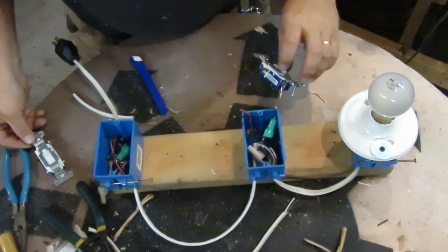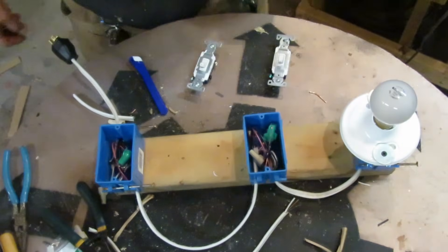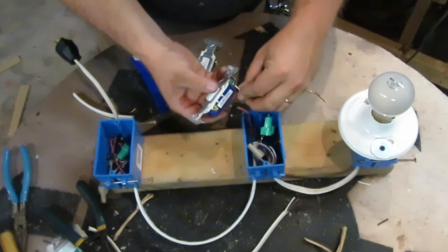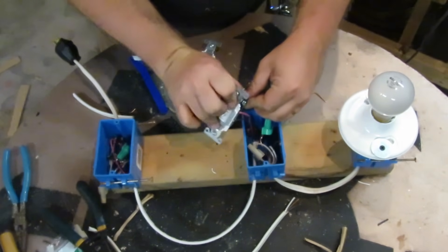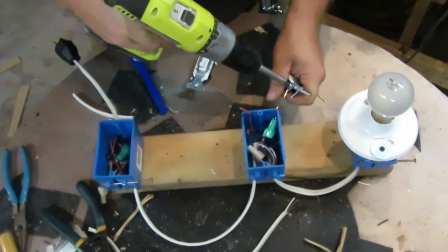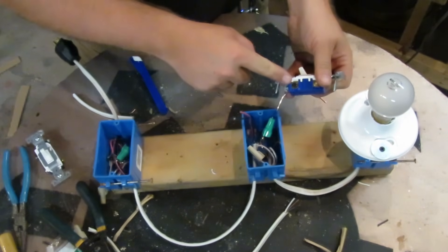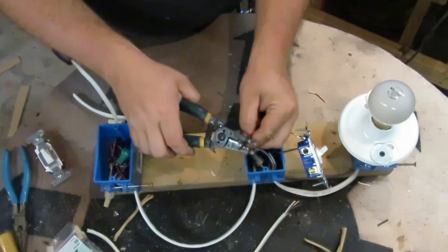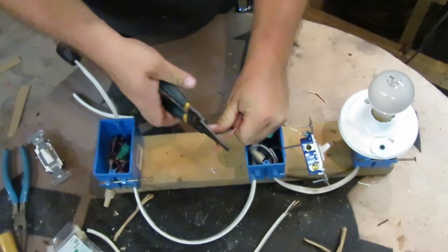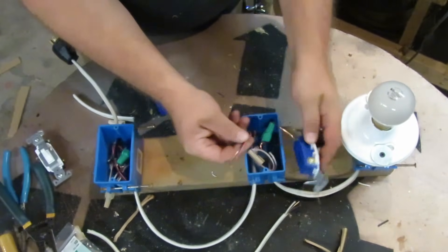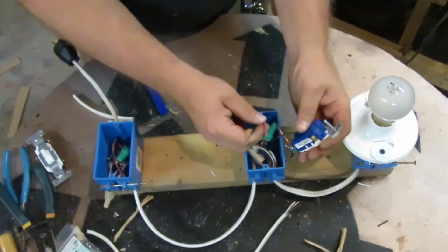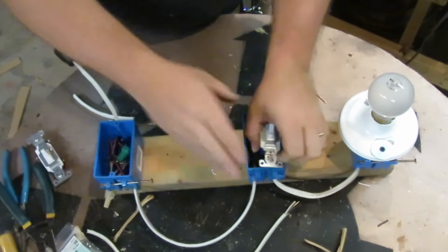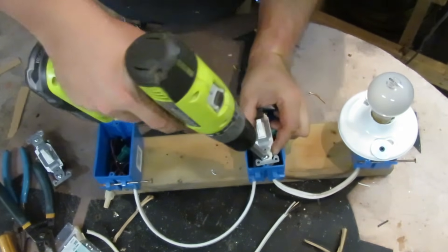And that's our switch line or our hot wire. All right, after you've hung your walls you come back to the box and you pull your wires out, and you want to put the bare copper wire to your green screw, and then your black screw gets your common wire which in this case is the switch line. And then you just want to strip out your two traveler wires and put one to each of those two brass screws, and then you're done with that switch.